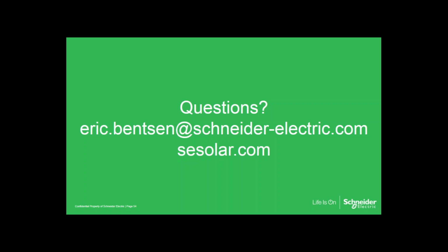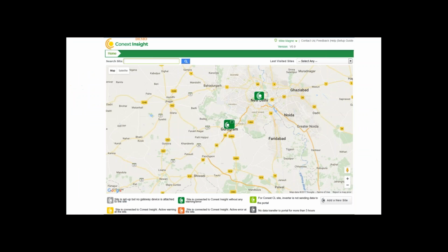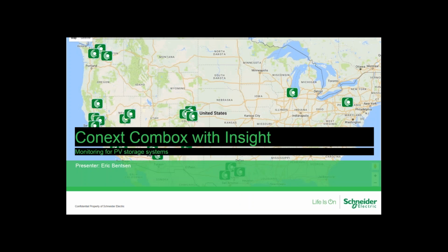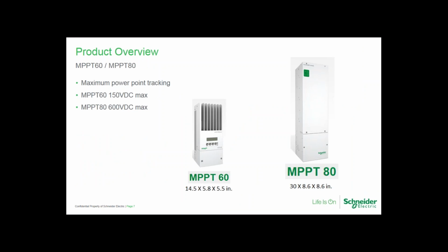Eric, our first question is going back to the charge controllers and asking what string sizes are allowed for the charge controllers? Oh, that's a great question. So we offer two models of MPPT charge controllers. Let me go back to the screenshot here. So the MPPT-60 is a relatively lower voltage charge controller. It accepts up to 150 volts DC maximum, and that's an absolute maximum. So you want to make sure that you calculate your record low temperature for the area that the system is going to be installed, and then calculate your maximum open circuit voltage.